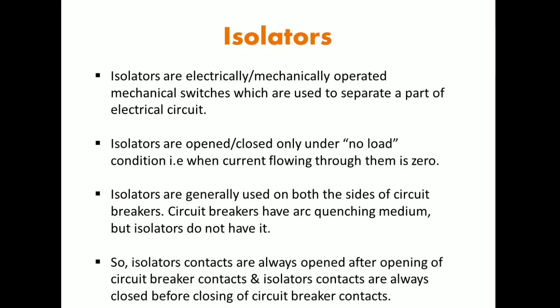Isolators are generally used on both the sides of circuit breakers. Circuit breakers have arc quenching medium, but isolators do not have any arc quenching medium. So, isolator contacts are always opened after opening of circuit breaker contacts, and isolator contacts are always closed before closing of circuit breaker contacts.